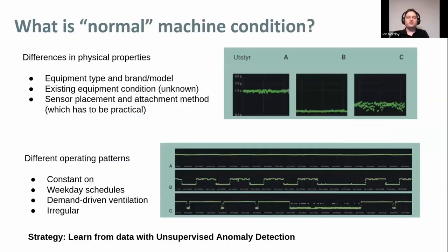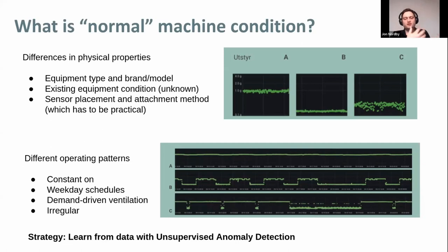We realized quickly that what is considered normal for a machine varies very much depending on the particular machine. There are variations based on physical properties such as equipment type, brand, and model — even within the problem space of air handling units — as well as sensor placement and attachment method, which needs to be adapted to a particular device since they're not designed for mounting sensors on. There's also the existing equipment condition, which is often unknown before starting condition monitoring. There are also differences in how equipment operates: some things are constantly on, some have a weekly schedule, some are based on sensors like CO2 sensors from the room, and this gives much variation.